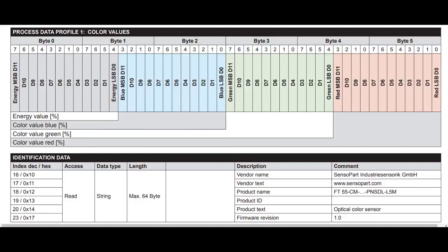And you can see here in IO-Link, you have the energy value, the blue, green, and red data. So you can set up the tolerances like color mode in your PLC. And again, let the sensor do the best fit.